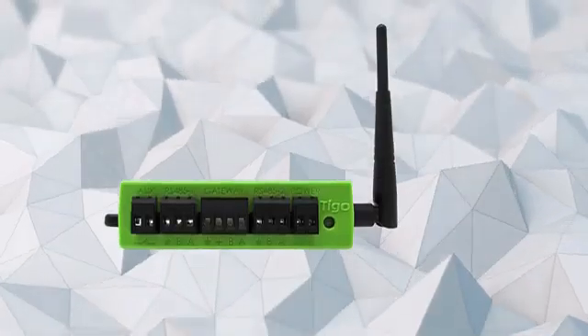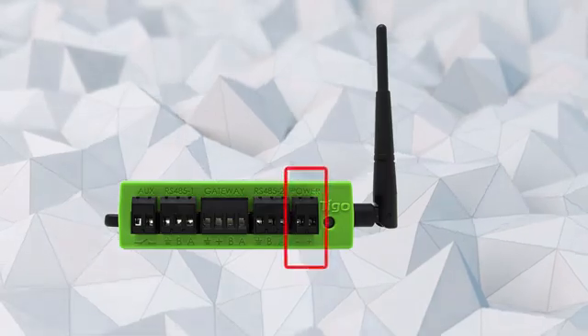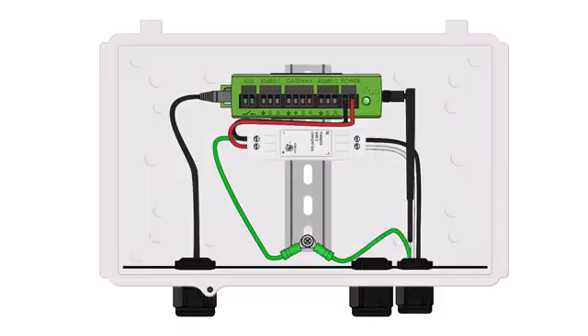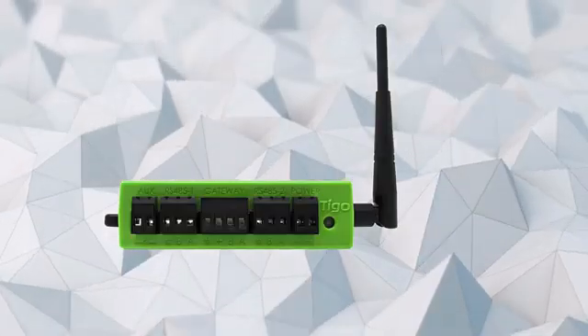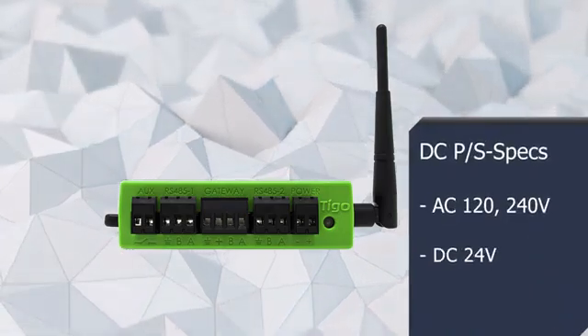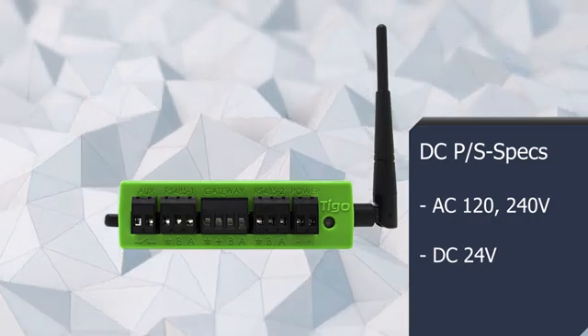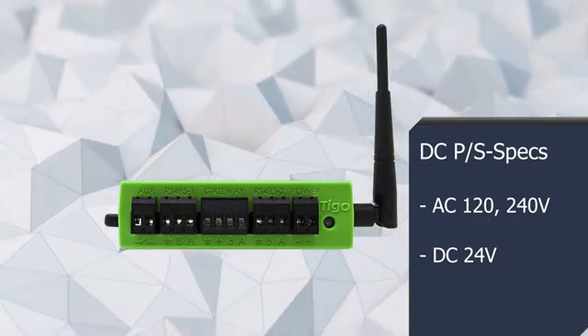Lastly, it is time to connect the CCA to the AC power source. The CCA requires a 24V 1A power supply that must be connected to the AC breaker or equivalent. This power supply is available from Tigo. If you use your own power supply, the input voltage must be between 100 and 240V AC, and the output must be 24V and 1A.